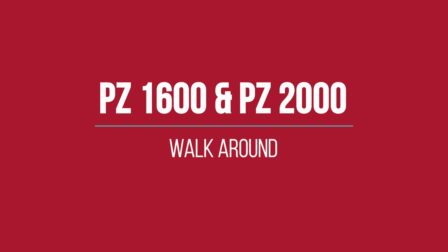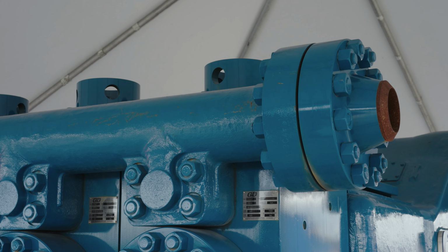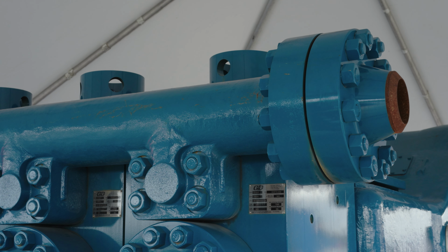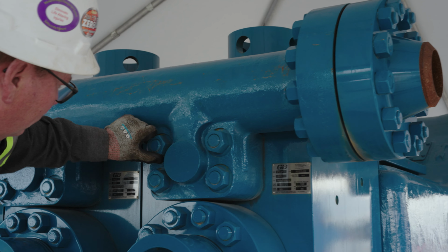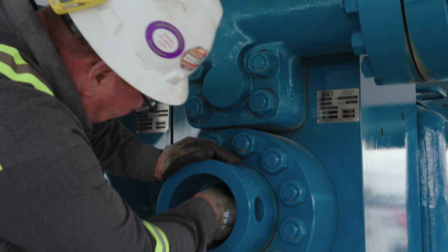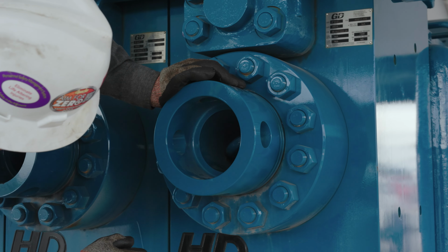First, you want to inspect and make sure all threads on studs and nuts are evenly displayed with no signs of loose nuts on all rings, manifolds, and flanges. Checking for correct torque value is suggested at least twice per year.